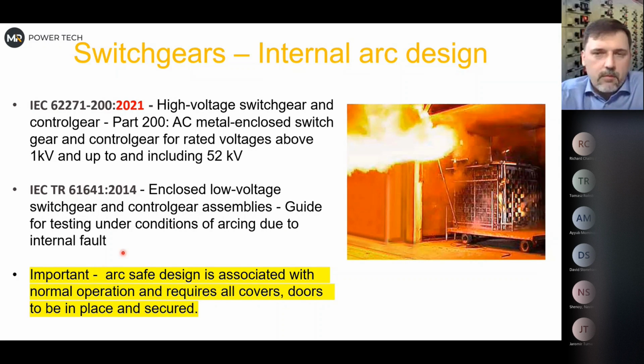But it's important to remember that behind all the internal arc classification and hardware related to switchgear, it is associated with the fact that the design of everything is done for normal operation or normal switching operation. So if something happens inside the panel, it has to stay inside. We'll show you videos. But you have to keep in mind that all doors and covers that have to be secured, they have to be secured. Otherwise you might lose this arc classification.